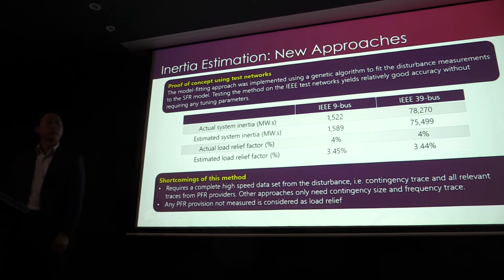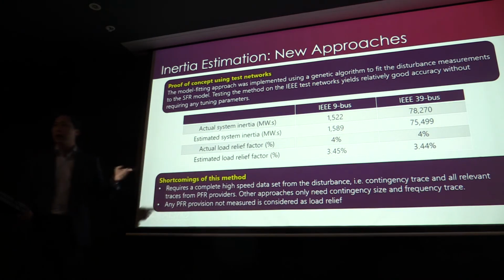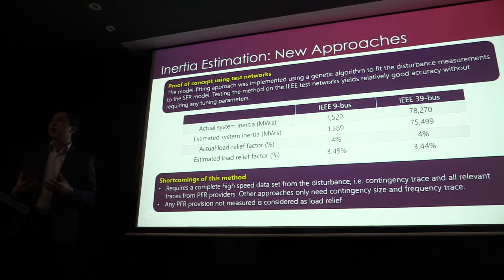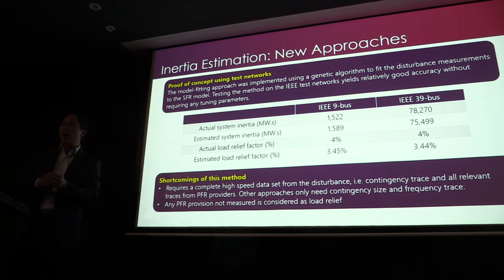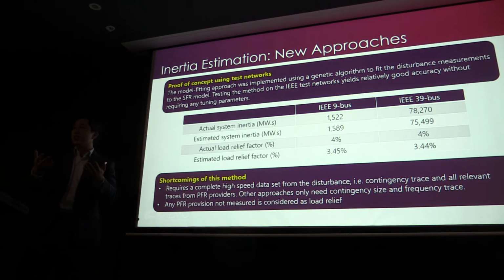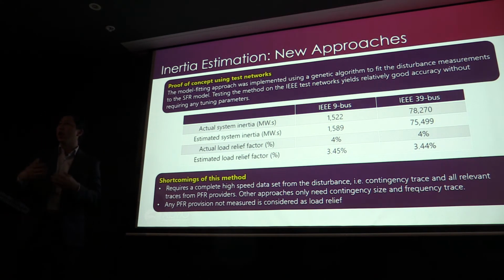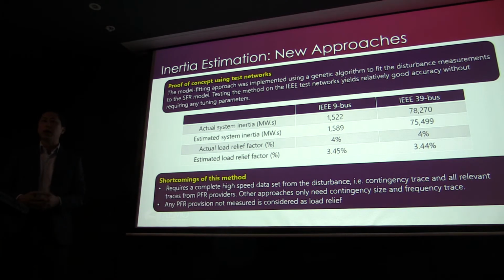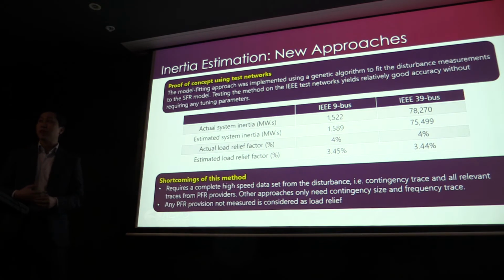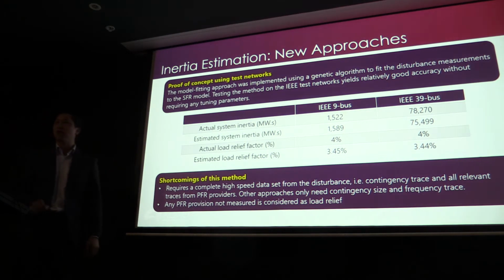Can you explain the load relief? Is that load trips or is that controlled load shedding? Good point. Load relief is a property of induction motors primarily, where the power output is proportional to frequency. As frequency drops, their torque drops, and then the load goes down. So it relieves the load, if you will. You get a reduction in load because induction machines are slowing. This is mainly material to industrial plants and mining. Houses with air cons tend to use inverter air cons, so they don't have that much load relief. So you don't get a lot of load relief in residential loads, but mainly from mining loads. If you were to look at, for example, a desalination plant, they have a perfect load relief curve because it's all induction motors, and they're about 4 or 5% relief here.